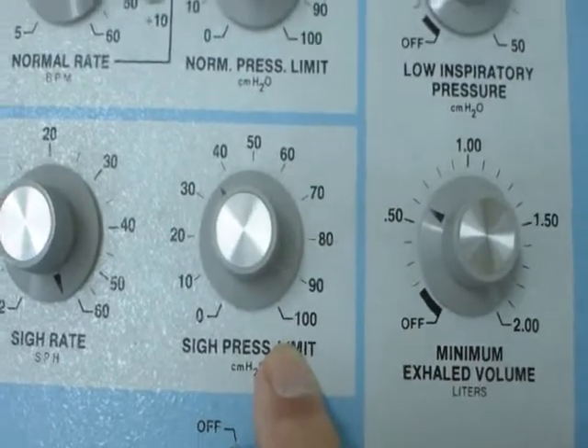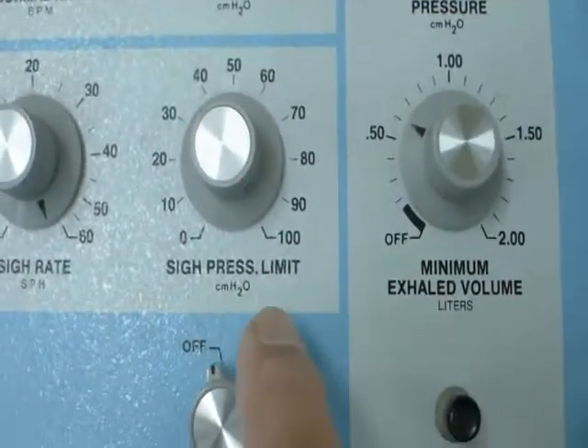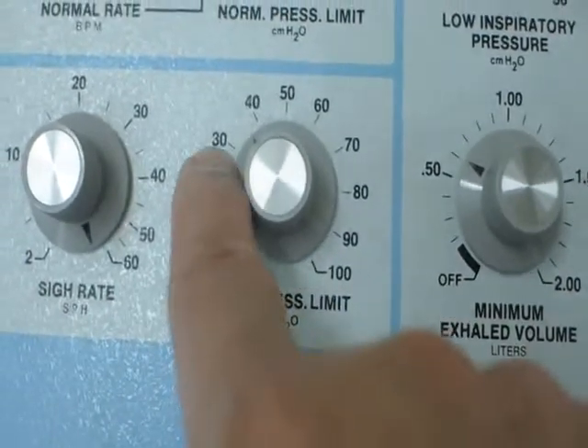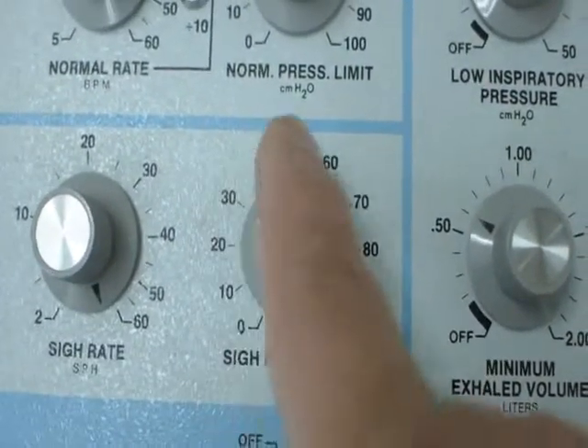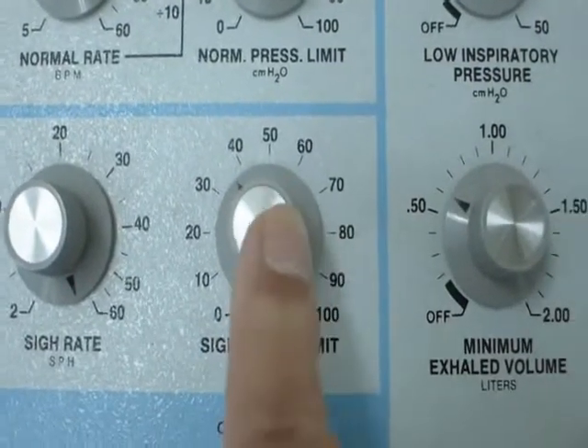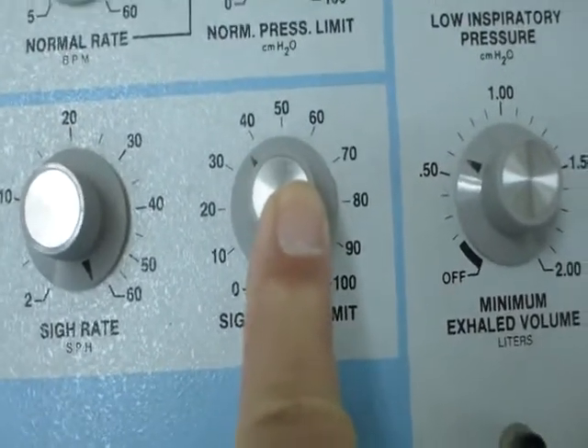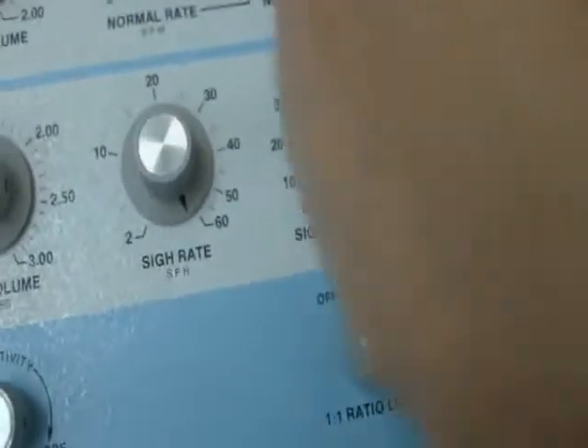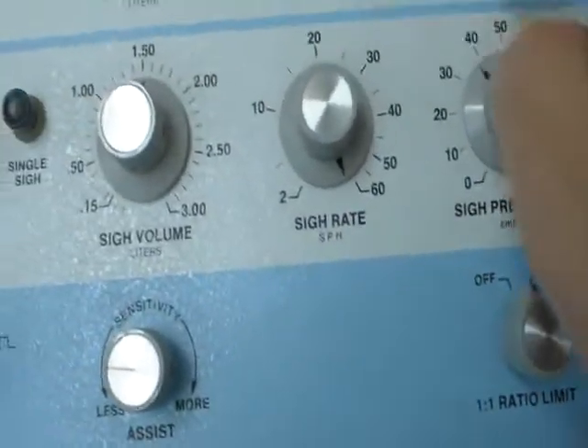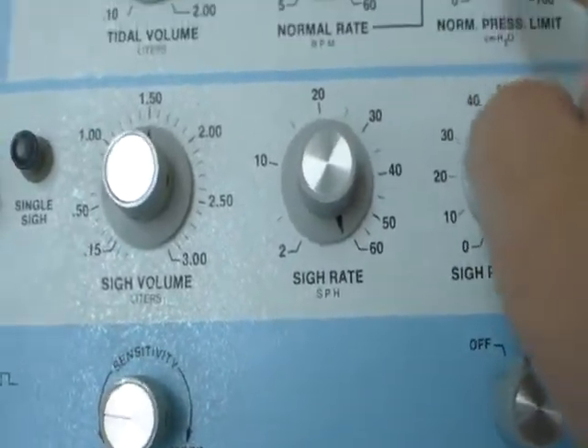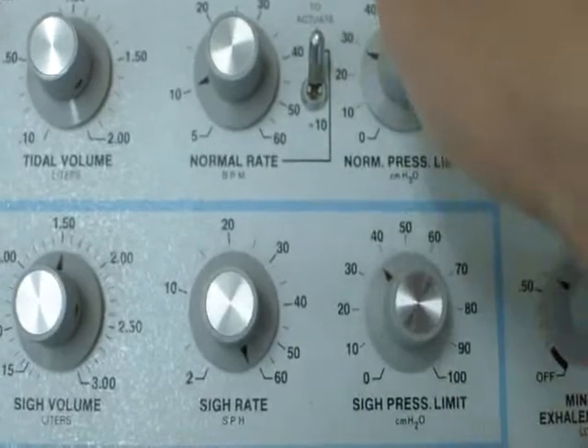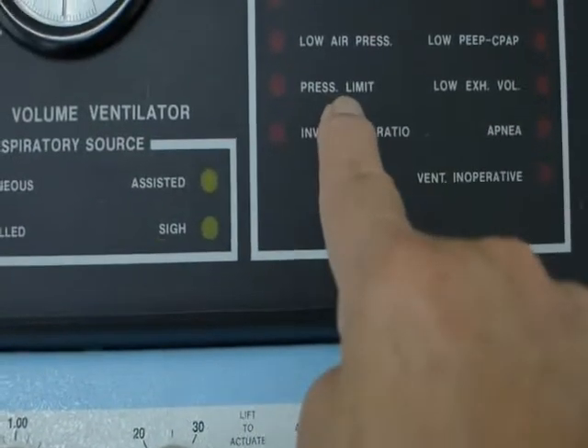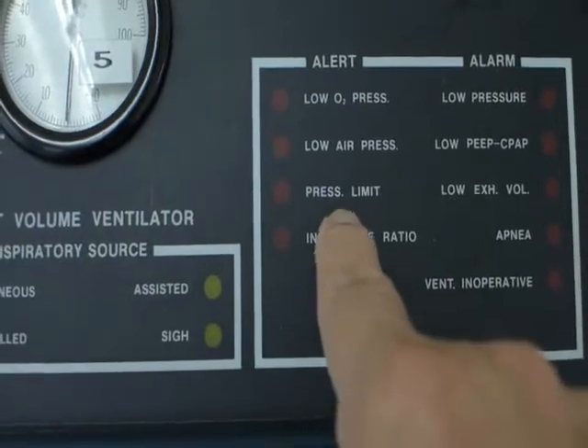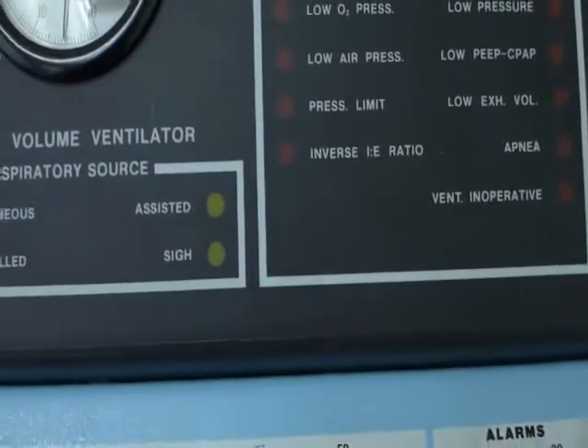But the thing is, this one will actually give you some sort of alarm, because when you have a limit, if the sigh pressure hits the limit, it's going to alarm. Okay, as the pressure limit. It's the same thing as the normal pressure limit. Anything that sets off the alarms is going to go to the pressure limit LED indicator here. The pressure limit is going to alarm to tell you that, hey, there's something going on with the pressure limit that you're setting. All right. Okay, and then we come over here.